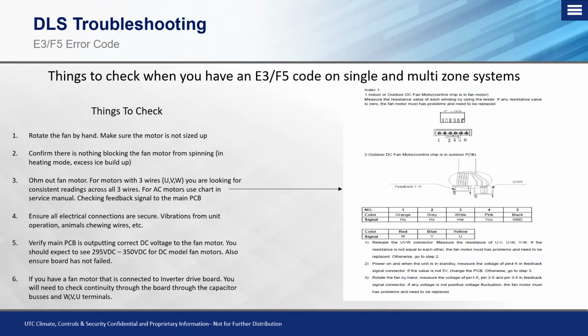And once that happens, you'll see that the fan motor does this little shimmy and shake. A lot of guys ask what that is. What we're doing, from that main PCB, or from the inverter drive board depending on the system configuration you have, is what's called a rotational reference. We're pulsating DC voltage to that fan motor to essentially figure out the correct direction to spin that fan motor so it does not run backwards. So when you see that pulse, that shimmy and shake of the fan motor, that is a rotational reference.